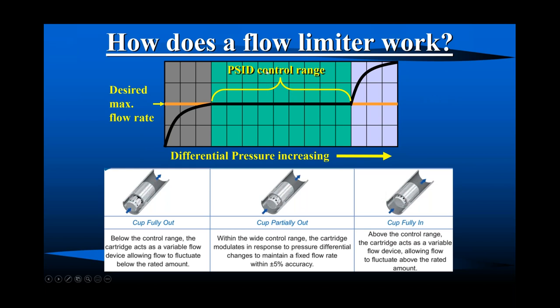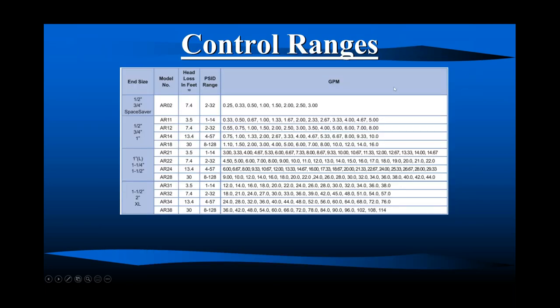So let's talk about this control range. This is a chart from a manufacturer of automatic flow balancing valves. Here is the GPM that can be cut from the factory. The lowest one is 0.25, 0.33. So if anyone's had to try to balance one GPM through a 3/4 inch pipe, this is a lot easier. Just get it cut for one GPM.